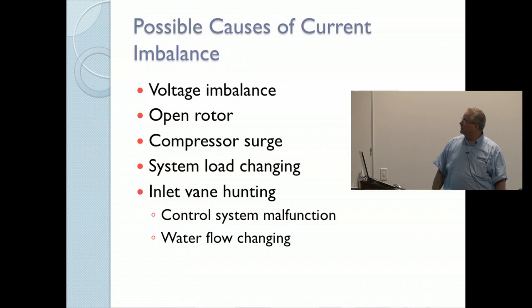Possible causes of current imbalance. Voltage imbalance, we just talked about that. Open rotor, pretty rare. It's just a defective iron in the rotor of the motor itself. Compressor surge, if your compressor is surging, you're going to see imbalances.